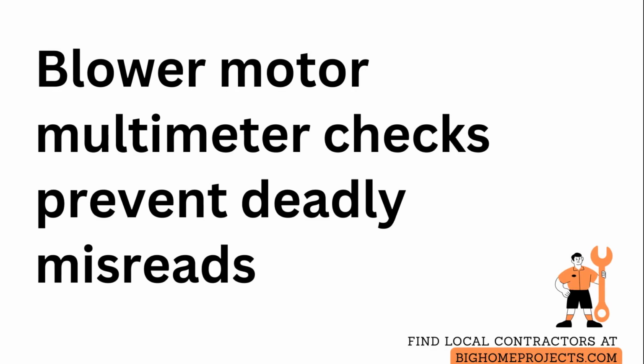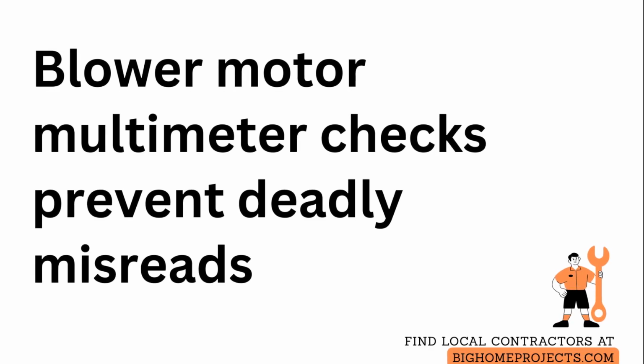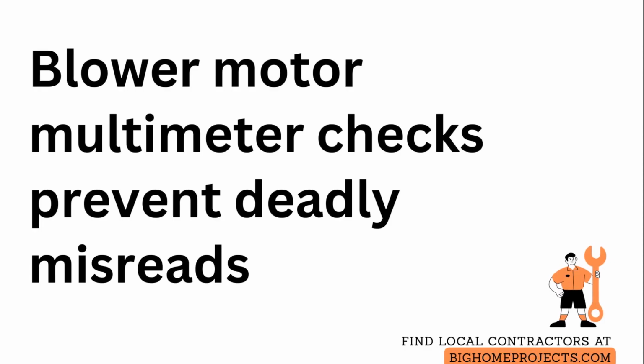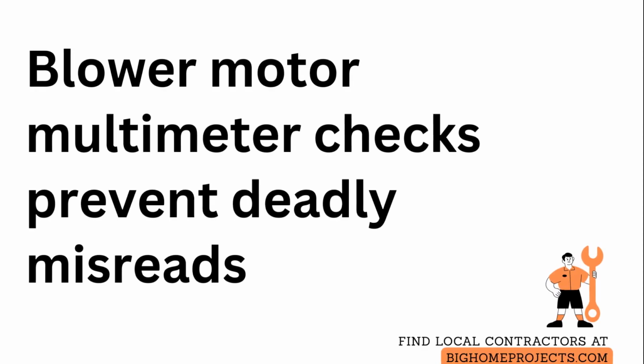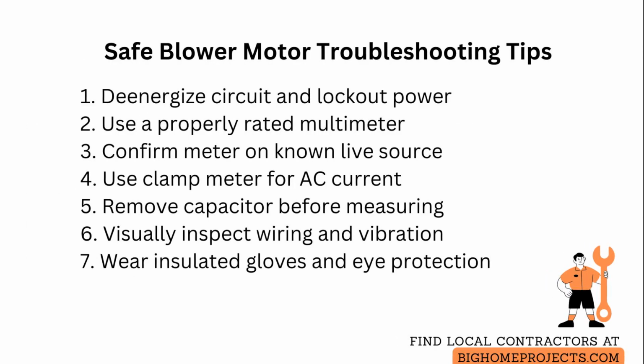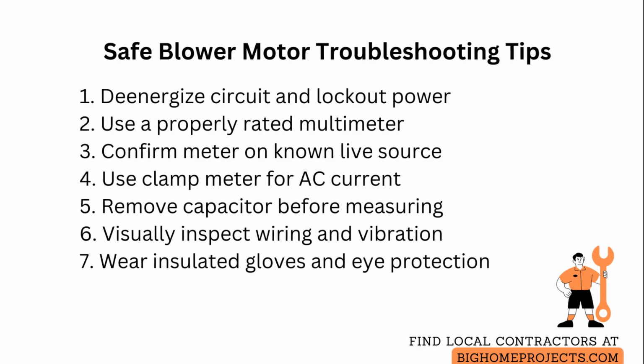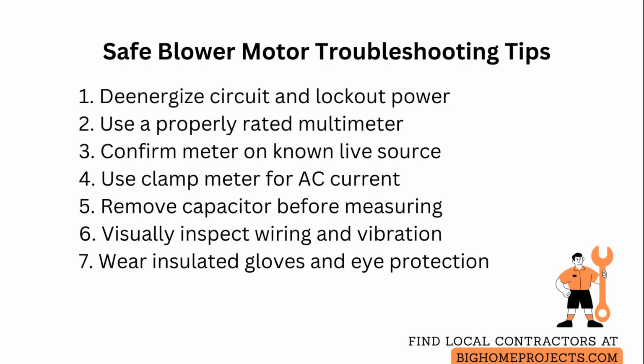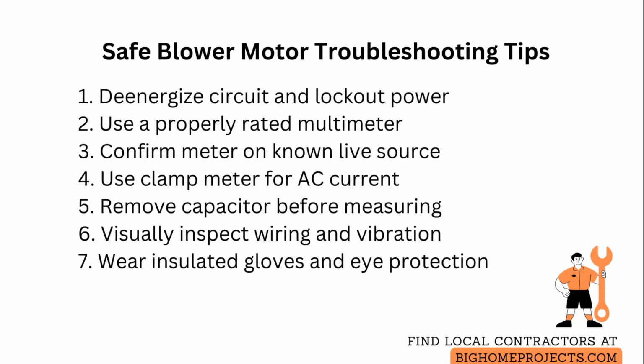Troubleshooting a running blower motor without a multimeter is an unsafe and avoidable risk that can lead to shock, equipment damage, or misdiagnosis. A blower motor is an electrical device that draws current, spins a fan, and often connects to capacitors and control circuits, so start by de-energizing the circuit and locking out the power before any hands-on inspection.